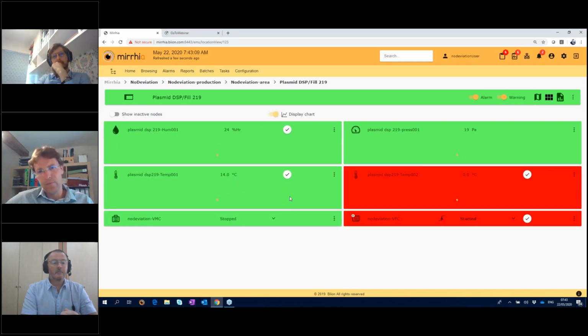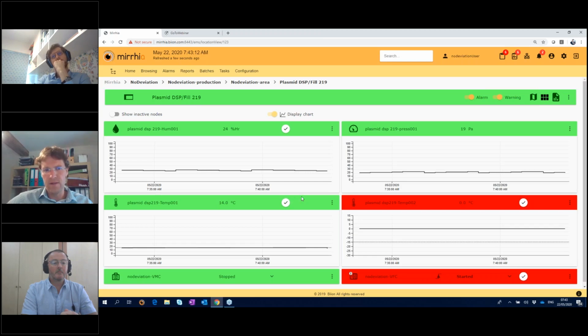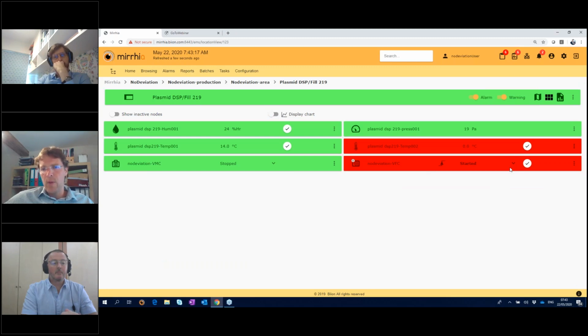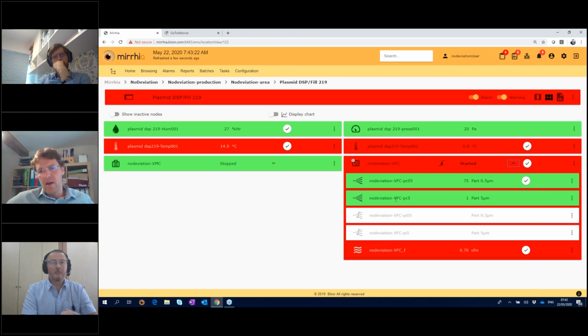If I want, I can have a trends chart that's live updated. I can also see the detail of what's happening in my particle counter, because you can see that it is in alarm. Why is it in alarm? You can see that there are 2 channels that are okay, but I've got the airflow of the particle counter that is in alarm. This alarm is propagated to the particle counter, and because there is an arrow there, by configuration we decided it was really important, so we wanted it propagated to the room. So you see that the alarm is propagated to the room.